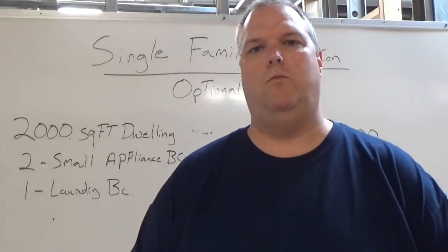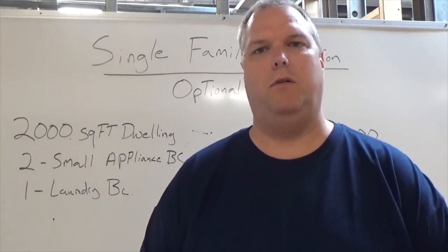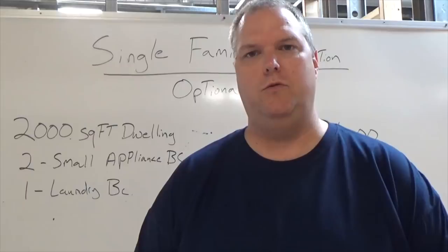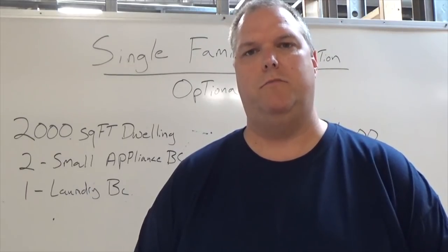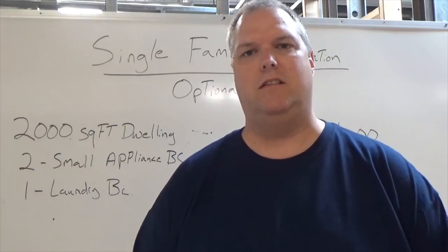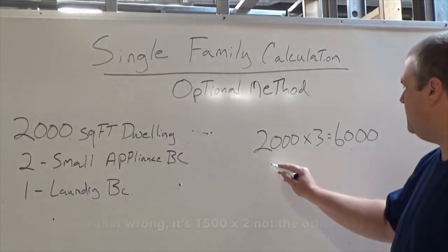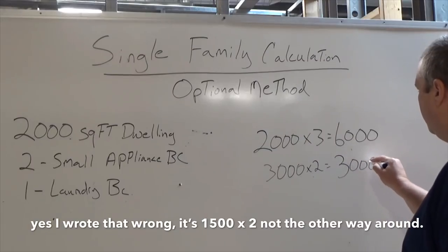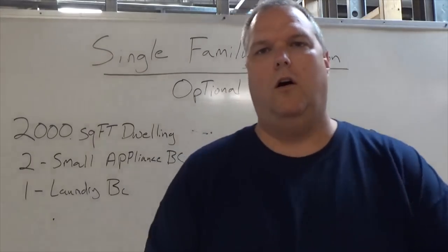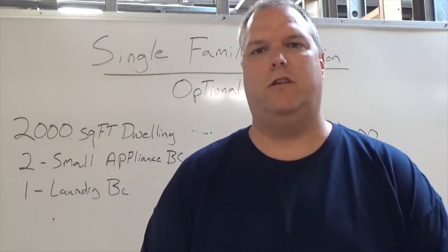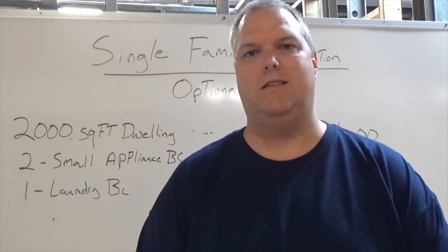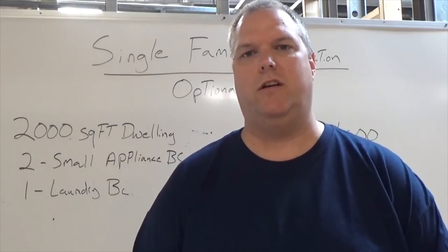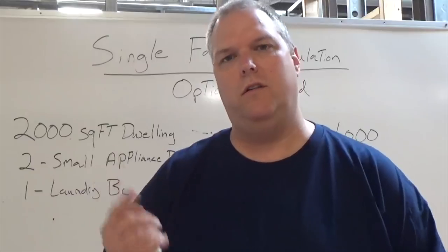We calculate our small appliance branch circuits at 1,500 VA per circuit. The minimum code requires two circuits, so we multiply 1,500 by two, giving us 3,000 VA. According to code, our laundry branch circuit is taken at 1,500 VA — this stays contained to the laundry room, and anything added beyond that is irrelevant here. We have one laundry circuit, so we add 1,500 VA.